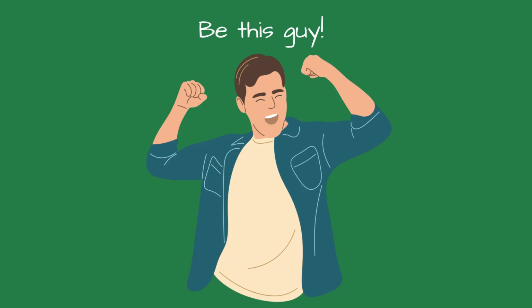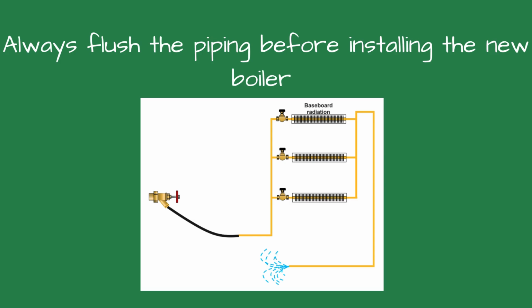Contrast that with the same system where the contractor flushed the piping thoroughly and tested the water before filling the boiler with fresh glycol mixed to the correct ratio. The boiler runs quietly, efficiently, and without corrosion problems for years. The difference was only a few hours of flushing and venting. Flushing a hydronic system before installing a new boiler isn't just good practice, it's a critical step that protects your investment, prevents corrosion, and ensures a boiler operates at peak efficiency. Failing to flush means gambling with premature failures, noisy operation, corroded piping, seized pumps, warranty disputes, and higher operating costs. For contractors, it can also mean return service calls and angry customers who wonder why their brand new boiler is already causing problems. Thanks for stopping by.